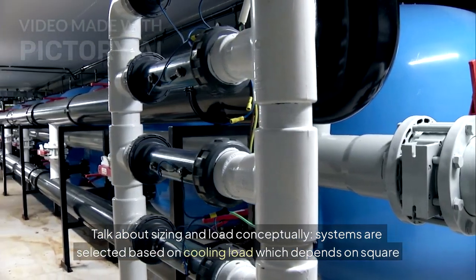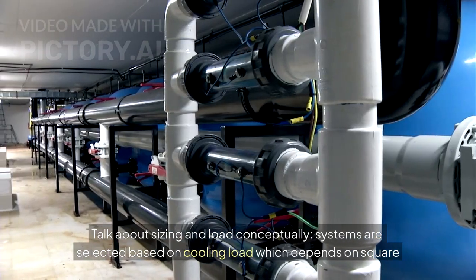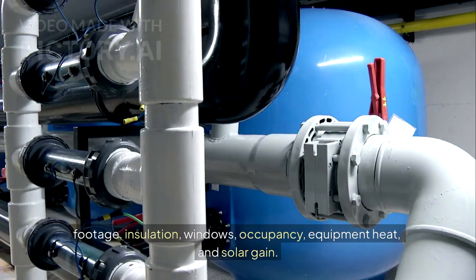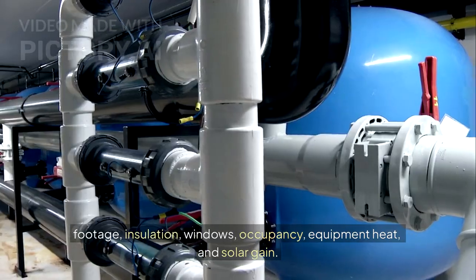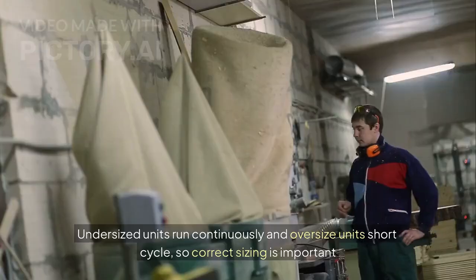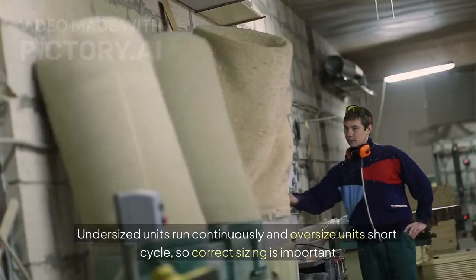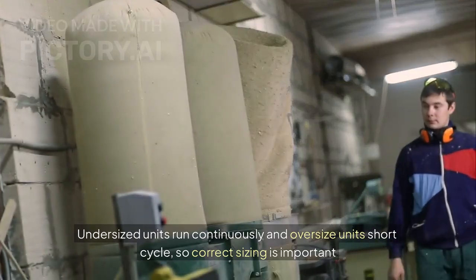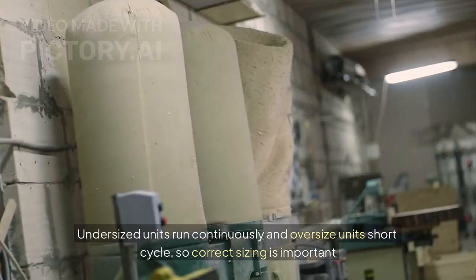Systems are selected based on cooling load, which depends on square footage, insulation, windows, occupancy, equipment heat, and solar gain. Undersized units run continuously and oversized units short cycle, so correct sizing is important.